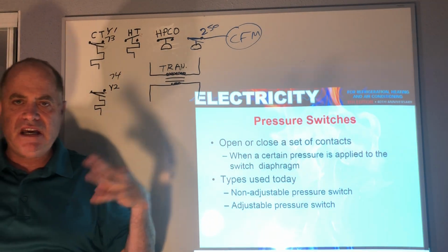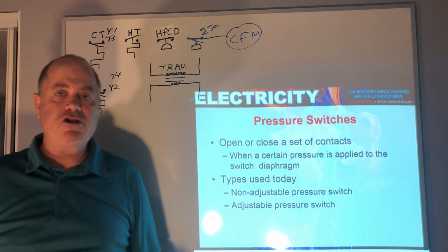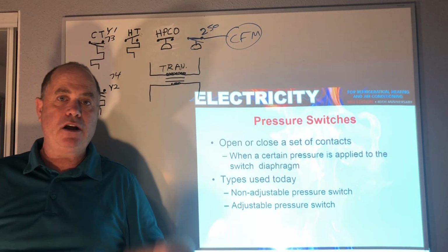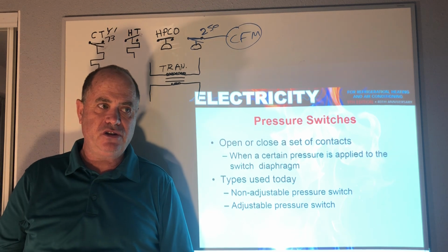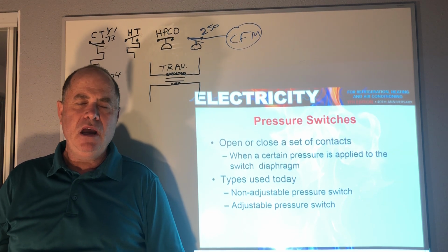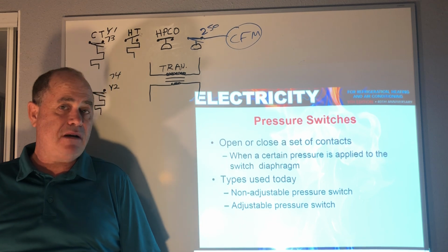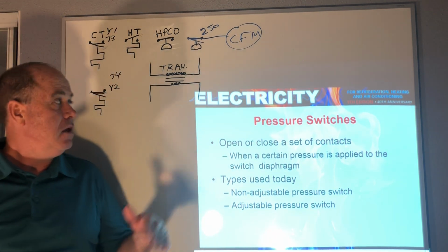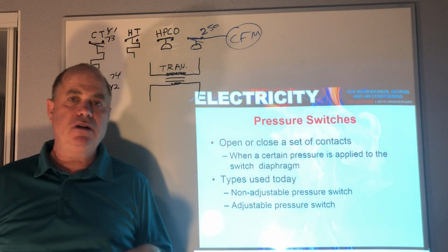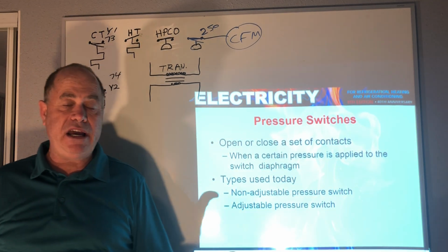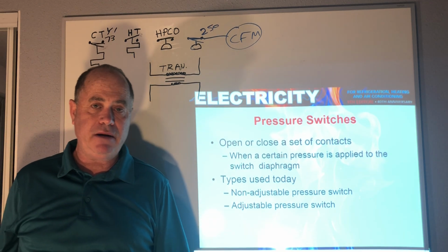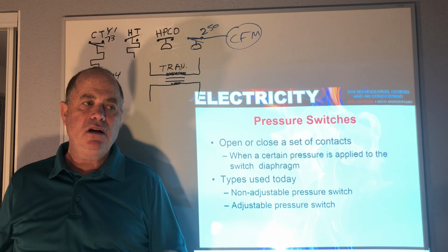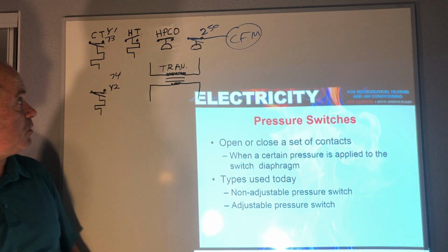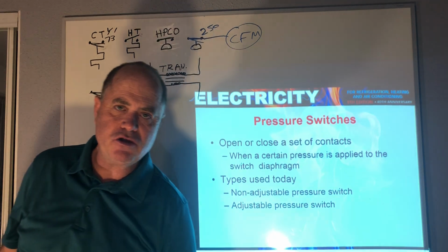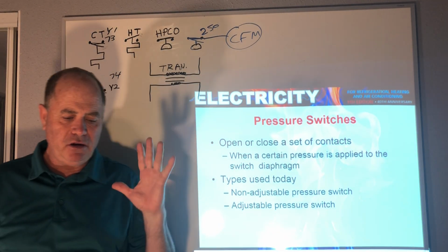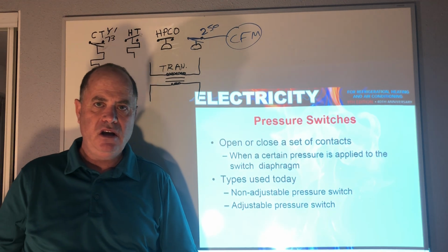And that 250 could be any number, but it makes and breaks on a pressure rise to bring on a second condenser fan, a third, a fourth. There are some air-cooled chillers with 12 condenser fans on them. We don't always need to run all 12, and sometimes we can get by with maybe 4, so we can activate them based on the pressure. If it's warm outside, or if the condenser is a bit dirty, you're going to have a higher head pressure. This helps maintain a nice, constant head pressure with these pressure switches. There are other pressure switches too, which I'm not going to go into, but those are by far the most common ones you're going to deal with.